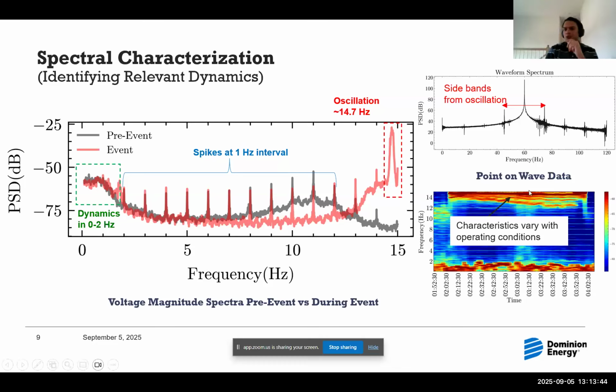We also checked with point on wave data because obviously the oscillation is very close to our Nyquist. So we wanted to make sure there is no aliasing problem, whether this is genuinely a 14 to 15 hertz, or 14.7 hertz to be precise, oscillation, or is it something else just aliased at 14.7 hertz.